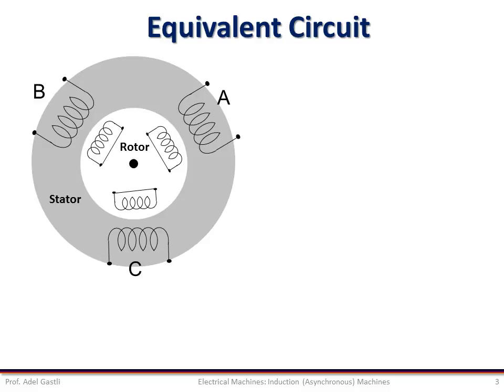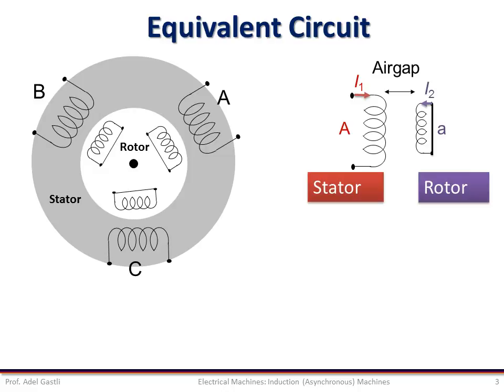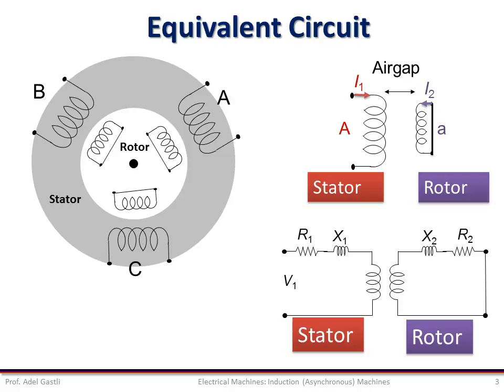In principle, the three-phase induction motor consists of six coils. Three coils are in the stator, as well as the short-circuit rotor, which is magnetically acting as if it consisted of three coils. It is possible to make an equivalent circuit diagram using only one set of three coils, or one stator and rotor phase. The AC impedance of each winding comprises a resistance R and an inductive reactance X equal to 2πFL, measured in ohms, where L is the inductance of the coil, measured in Henry.